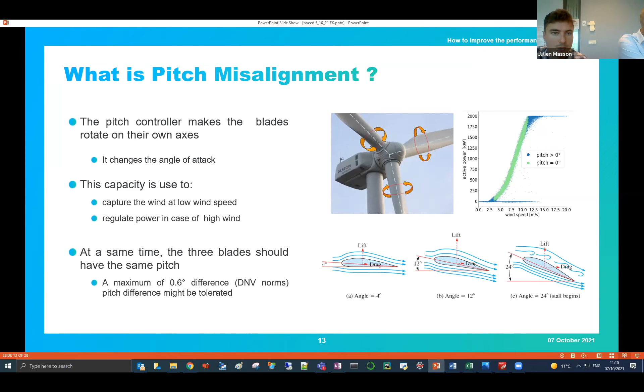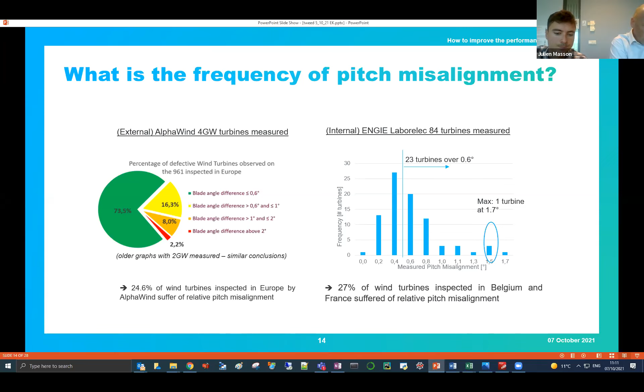So we have, for example, here an external study from a service provider that is measuring pitch misalignment on site. He measured more than 4 gigawatts of turbines, mainly in France and Europe, and he found out that a bit less than 25% of the turbines show higher than 0.6 degrees between 2 blades, and so suffered from pitch misalignment. From our internal studies with on-site measurements, over 84 turbines measured in France and Belgium, we found out that 27% were higher than 0.6 degrees. So it's quite frequent. And there is, of course, an impact.